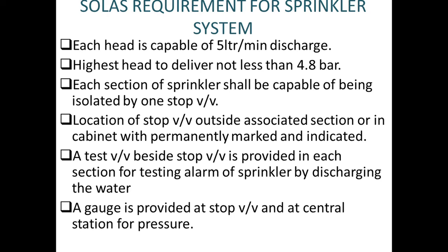So we are discharging the water and we are testing the sprinkler system. This test valve is beside the stop valve. Now a gauge is provided. Gauge means the pressure gauge we are talking about, at the stop valve and at the central station for pressure monitoring. So we have two pressure gauges, apart from the alarm and pressure switches.